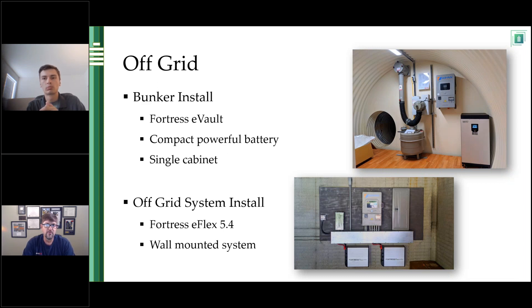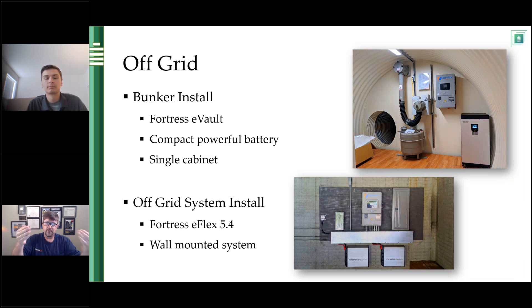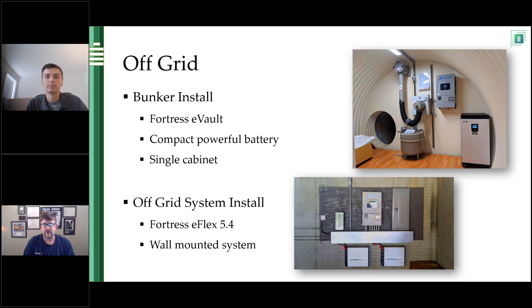I start really small and people are like 'you need more battery' — I know, but some customers can't afford more. I have several systems out there running on one e-Flex on a Sol-Ark 12K — that's not a great balance — but what did it do for them? They have water, they're off-grid, pumping water, everything's a bit limited, but we programmed the inverter so it's not beating up that e-Flex battery. It works fine and they're going to add a battery next year when they can afford it. The scalability of Fortress batteries and LFP chemistry is awesome — it allows people to get into solar battery backup because they can afford it now and scale up later.